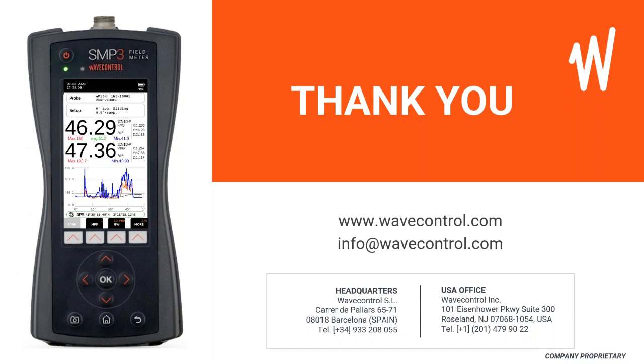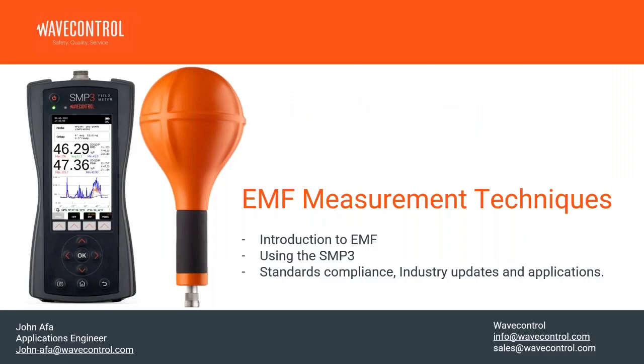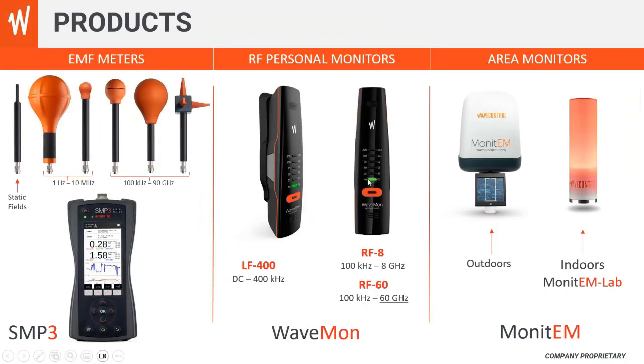With the WaveMon, it gives you a percentage with respect to the limit. You can see levels of 10%, 25%, 50%, 75%, 100%, 200%, compared to the standard limits. It allows you to switch from general public limits to occupational limits, and gives you the level compared to the standard limit. At 10-25% you get green LEDs, above that at 50-75% orange LEDs, and once you reach 100% or 200% and above, up to 1,000%, it measures from 0.5% to 1,000% of the standard limits.